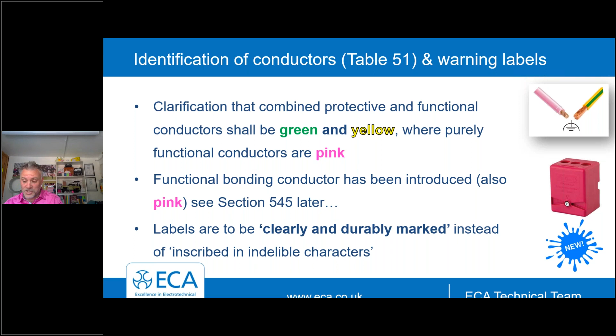Part 5 has seen the most changes, so selection and erection of equipment. Table 51 has been updated, with clarification that combined protective and functional conductors shall be green and yellow, and where purely functional, they are to be the colour pink. Functional bonding conductor has also been introduced. That is also pink. We'll come on to section 545 later. And a little note there about labels to be clearly and durably marked. So chapter 5 is where most of the changes now occur.